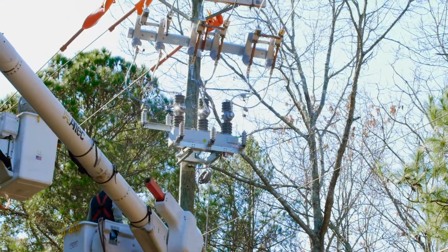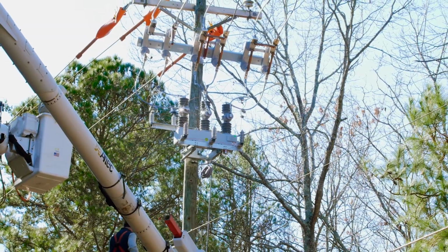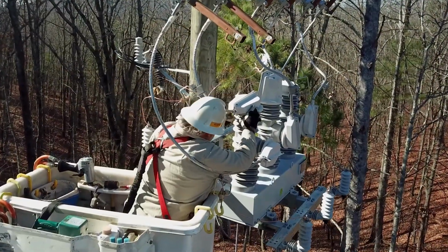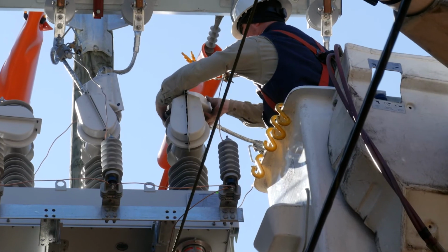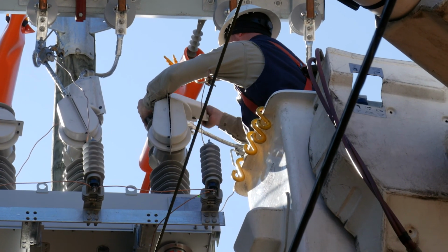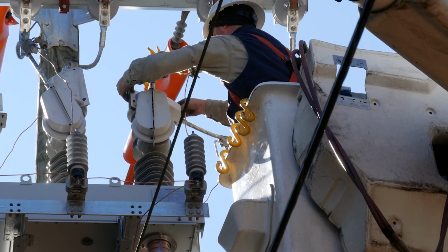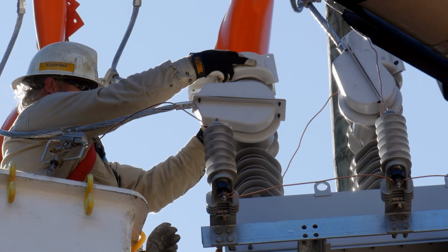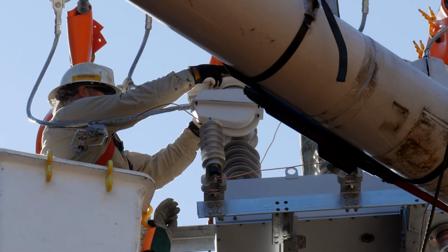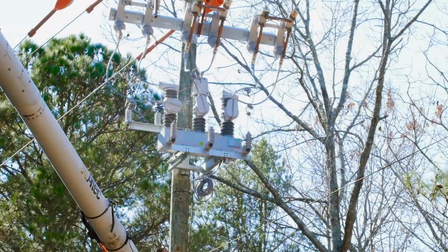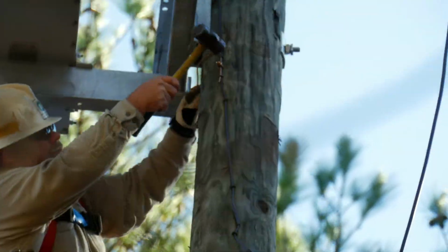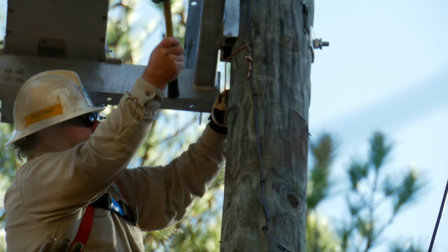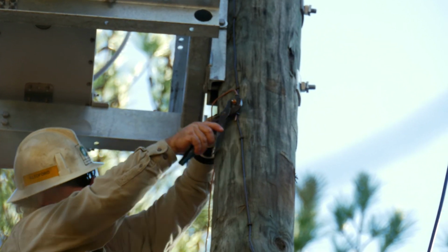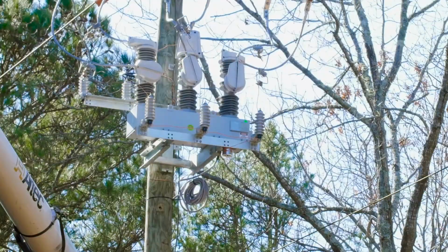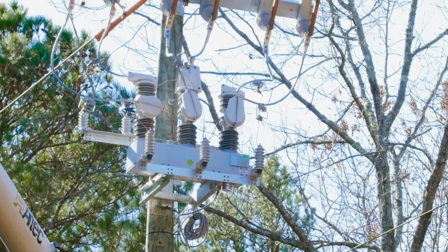With the base recloser installation complete at the top of the pole, the final optional step for a utility is the installation of wildlife guards. These help to provide protection against squirrels, birds, snakes, and other wildlife that can get between phases and cause an undesired operation. For total protection, jumper hose can also be added to the jumpers from the recloser up to the bypass disconnect switch. With everything at the top of the pole wired into the grounding lugs, it is time to run the ground wire up and connect it to the recloser mounting bracket. The ground wire ensures the recloser mount, tank, and arrestors are grounded.